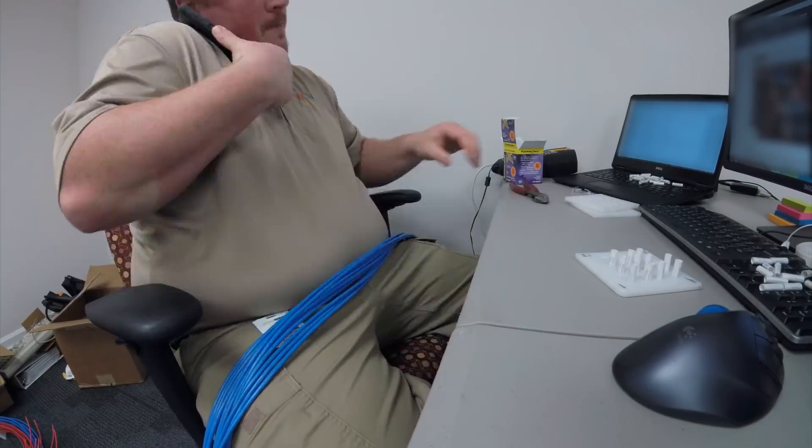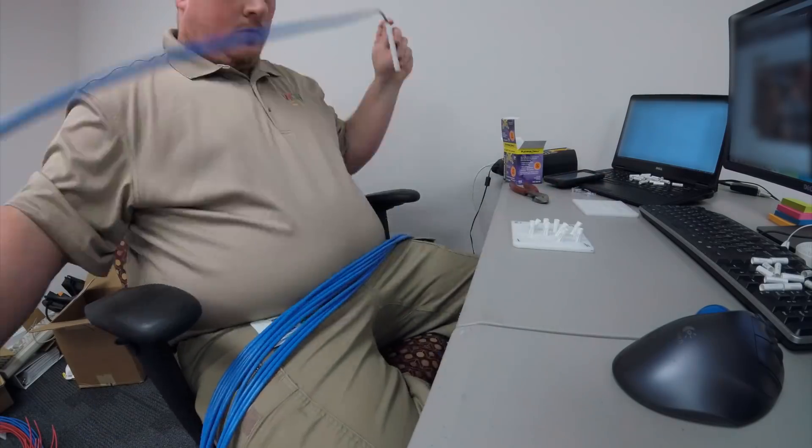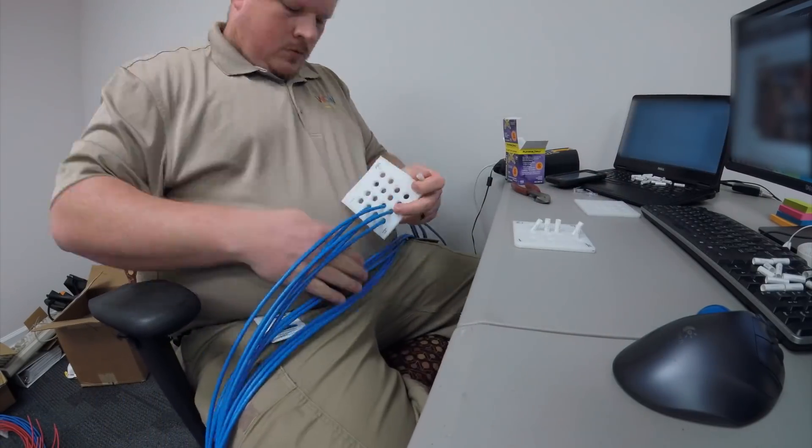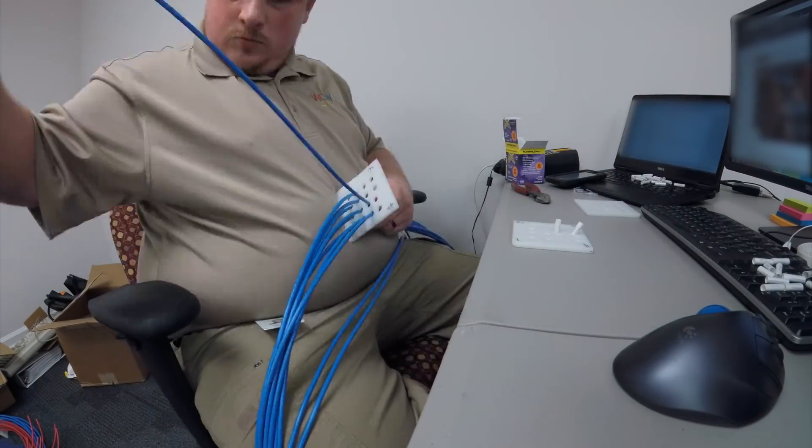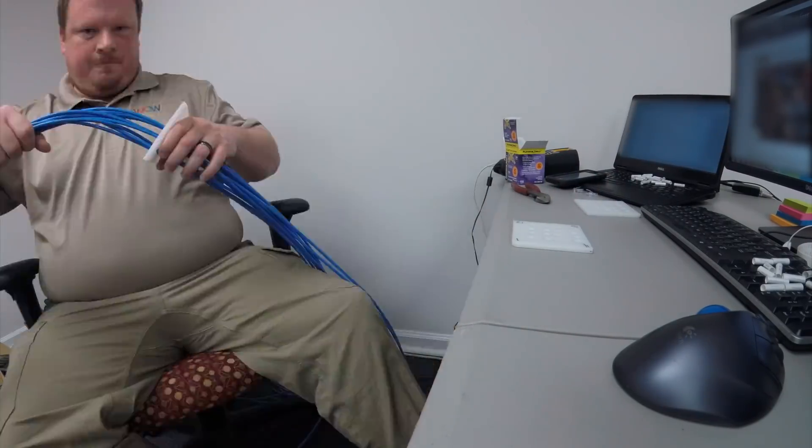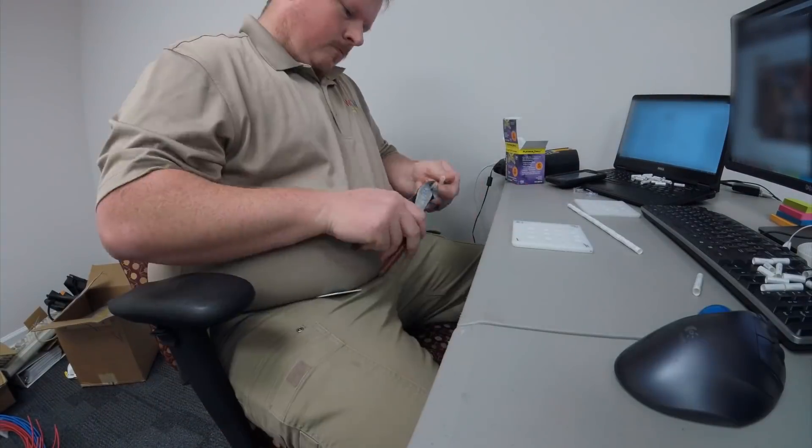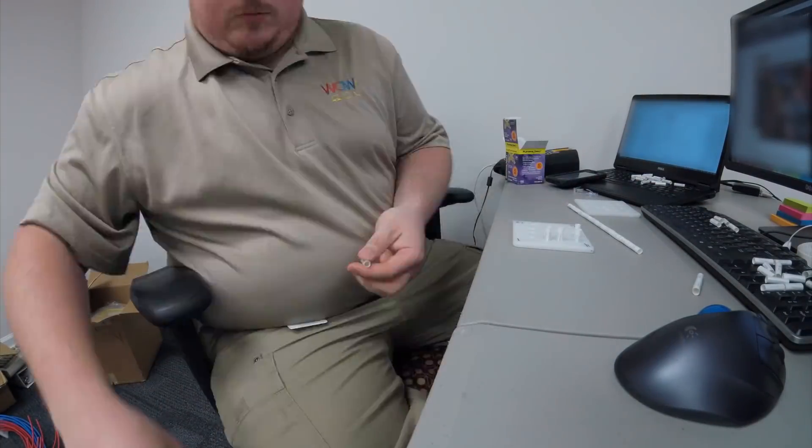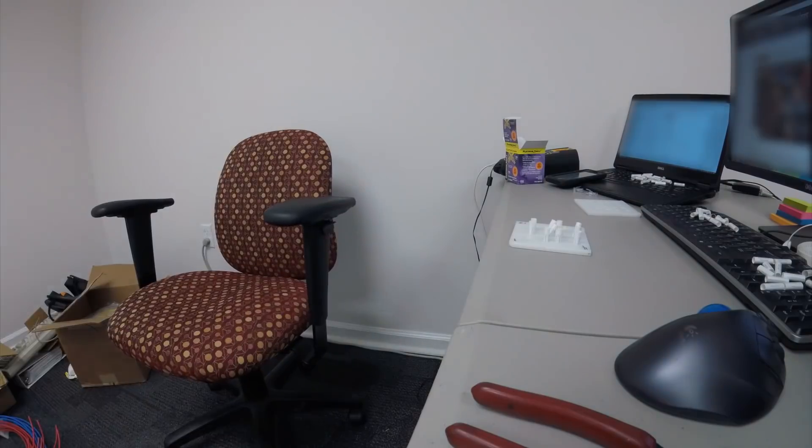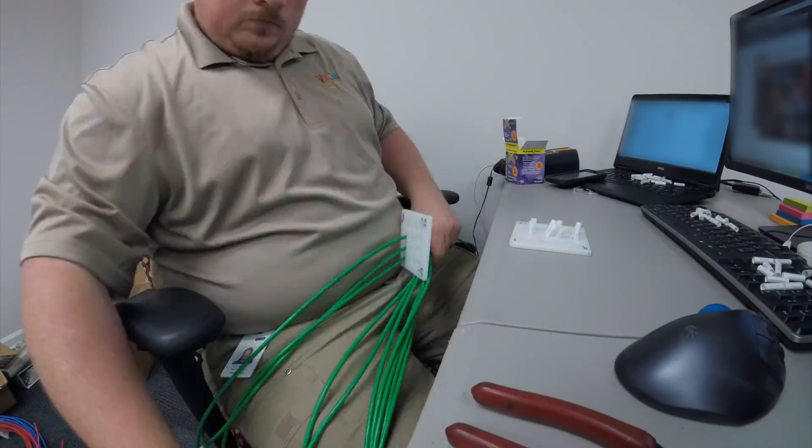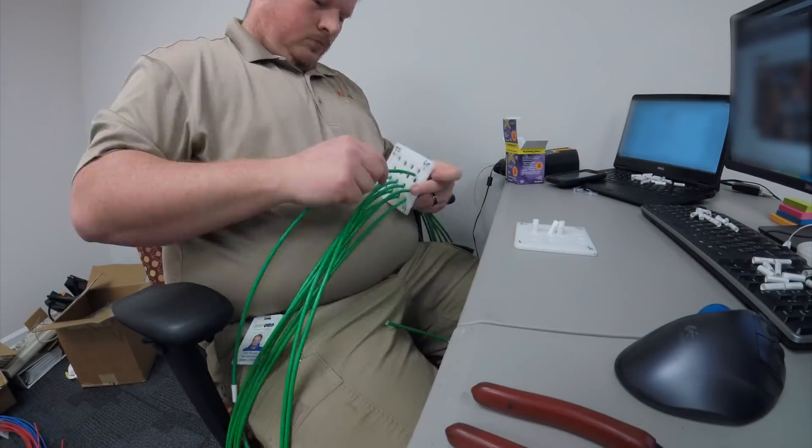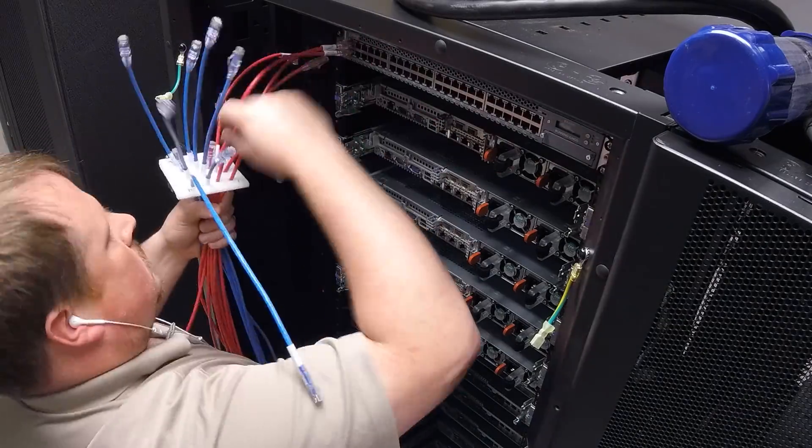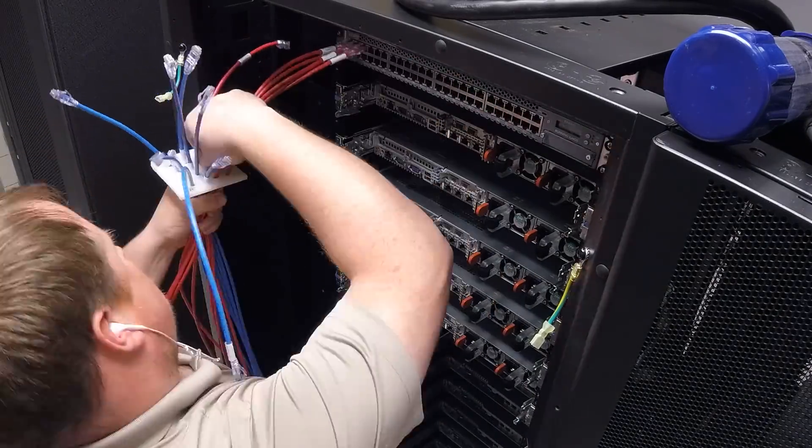For these I'm putting each cable in a cable comb. It's the white plastic you see in my hand. This keeps the bundle looking good, and it's also numbered so I know which cable goes to what server since I've not yet terminated or labeled the far end. This cable comb is simply some holes drilled in HDPE plastic, but you can buy these pre-made online.